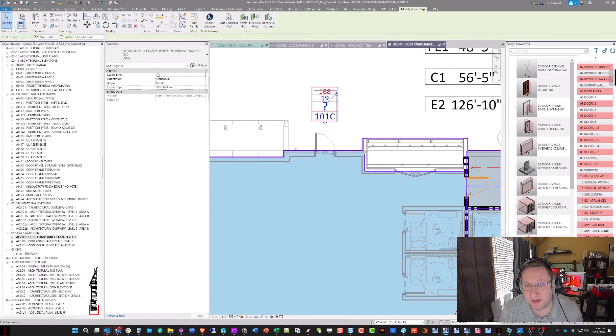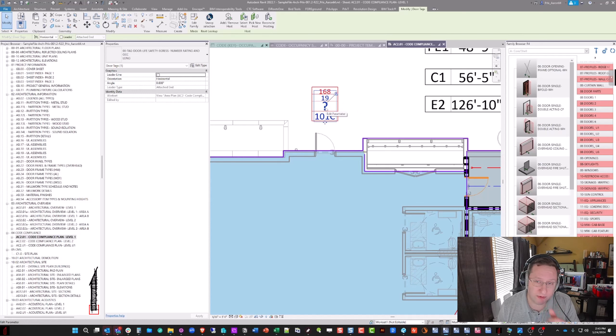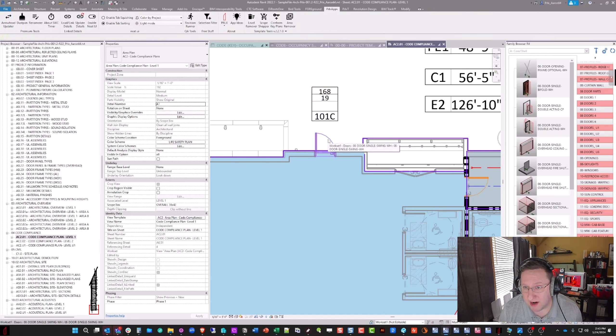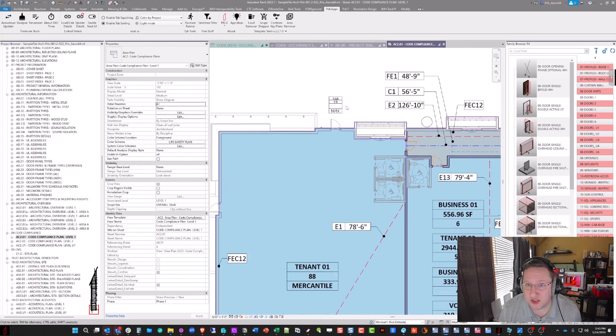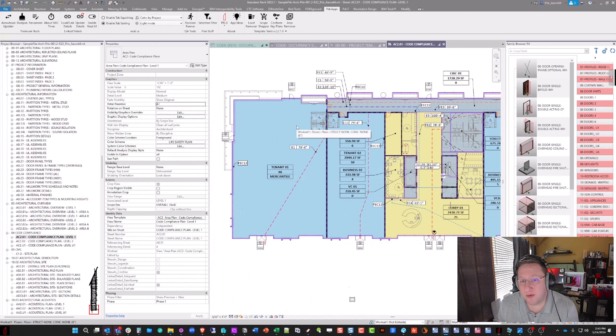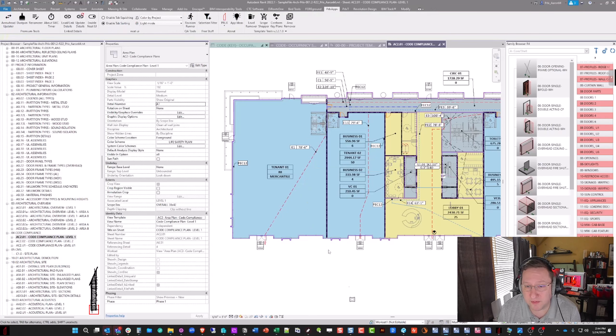As we get into the plan itself, in our version of the template there are area tags being shown — this is more a demonstration for clients so they can see what's possible. Because this is an area plan, we're reading areas instead of rooms. Those areas can have names and do have square footages. The areas themselves, based on the occupancy classification they're given, report the number of occupants in each area, though it's not a requirement to show that in the tag. In this particular case we're showing name, area, and occupancy count, but you can also just show name and area, or just show the name.